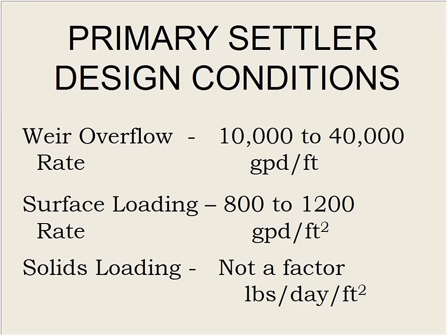So if it's in August, I'm going to be down around here. I may not be able to take some clarifiers off because I'm getting too low. I don't want it to be in there too long. Too long, it'll start to decompose. It'll generate gases. It's totally disruptive. Surface loading rate is another one. They're basically design factors. They're not anything a typical operator looks at on a daily basis. It's a design range. So yeah, how many clarifiers you're going to have, and it works back into your O&M manual. So when your flow's at this range, you want so many clarifiers. When it comes down here, you'll have fewer.